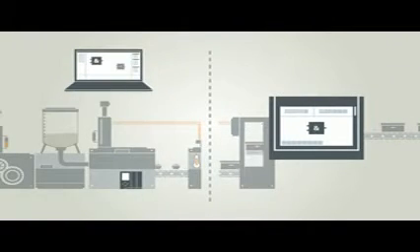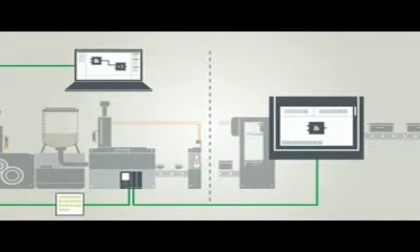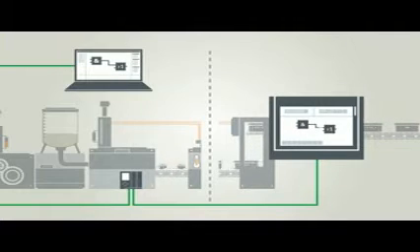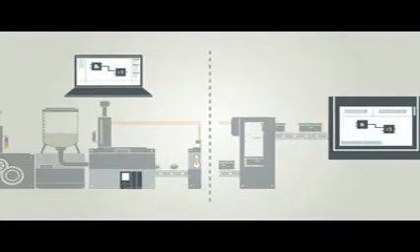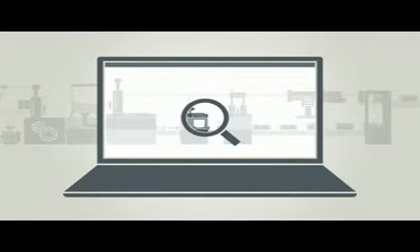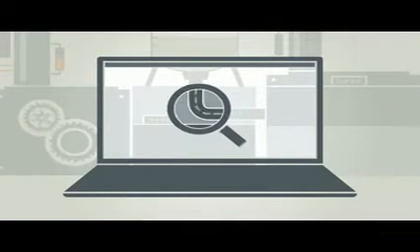Even program changes on the controller can be detected by the operating device, without having to reload the operating device. For supervision, you have a choice of various types of supervision in the TIA portal. With operand supervision, you primarily monitor static signals, such as pressure, and control supply voltage.